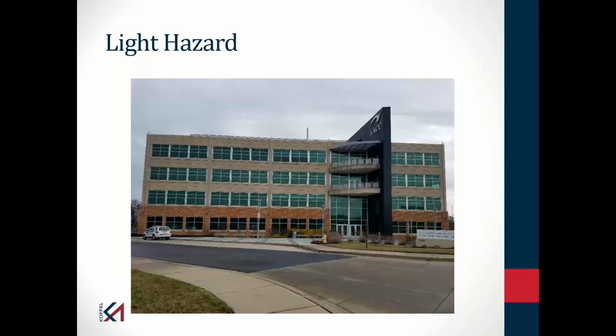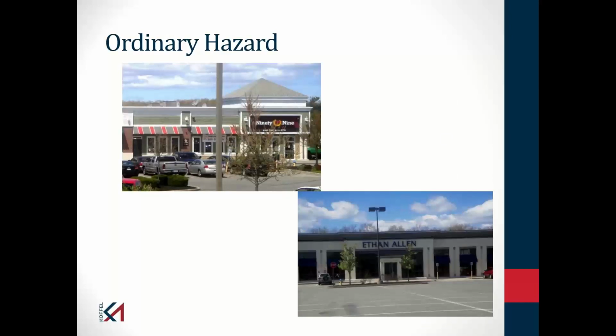Now, even within this building, let's assume this building is mostly classroom or office space, there may be some other areas that would be classified as ordinary hazard or extra hazard. So the ordinary hazard spaces that you are likely to find on a campus, you see in the upper left-hand corner a slide of a restaurant. Again, I already said the seating area is light hazard, but the cooking facilities, the kitchen area, where there's a higher concentration of fuel, would be ordinary hazard. Your bookstore, the mercantile, retail type locations on your campus are going to be ordinary hazard. So those are just 2 examples of spaces that would be classified as ordinary hazard.